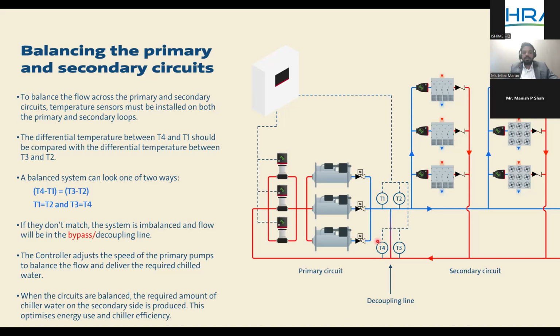Let's give an example. For a data hall, 20 and 29 are the supply and return temperatures. If the load is, say, 100 gallons per minute and the source is 100 gallons per minute, your T1 is 20, T2 is 20, and the system is perfectly balanced, and your T3 will be 29 and T4 will be 29. This is the ideal condition where we want to keep the system. The primary flow is exactly produced and driven to match the load on the secondary side. That's how we balance the circuit. It's not a manual balancing, it's a self-balancing system.